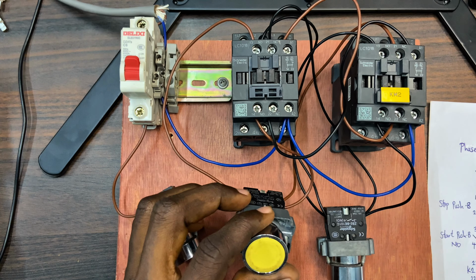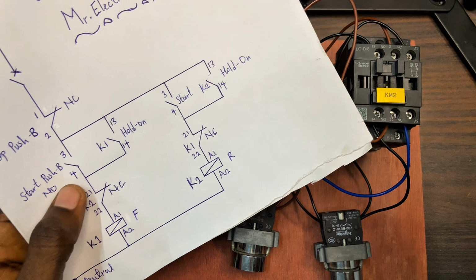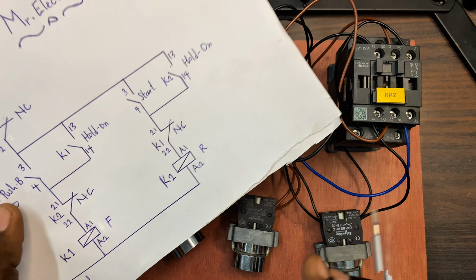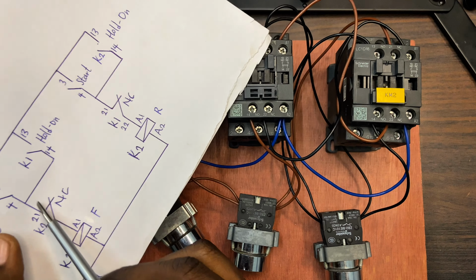That is the interlocking. We have interchanged the switch wire connections. This switch wire coming to A1 is being connected to the normally close we have on the reverse contactor before coming to A1. And at the same time, we have this switch wire coming to A1, that's the reverse contactor, being connected to the forward contactor normally closed before coming to A1 we have on the reverse contactor. That's the interlocking.